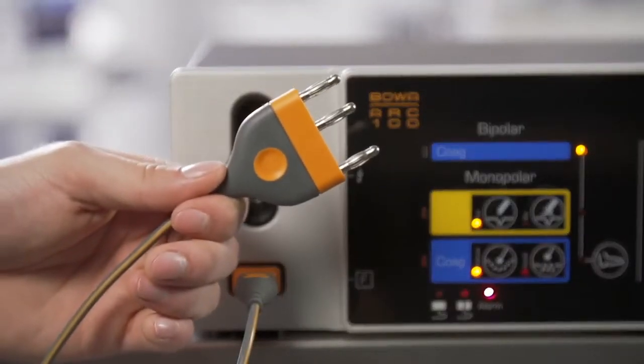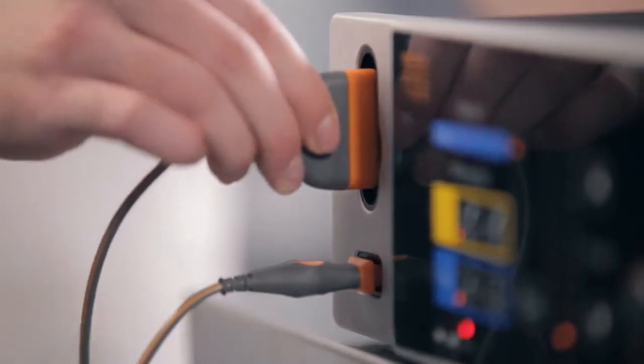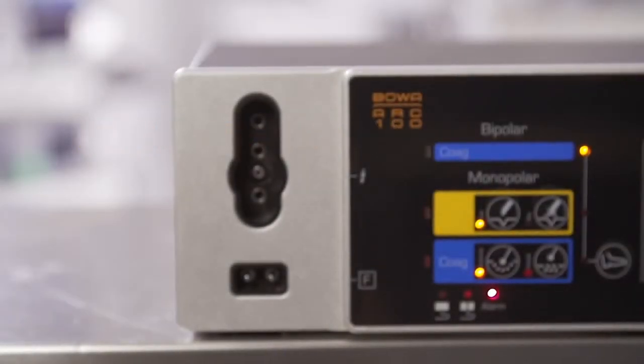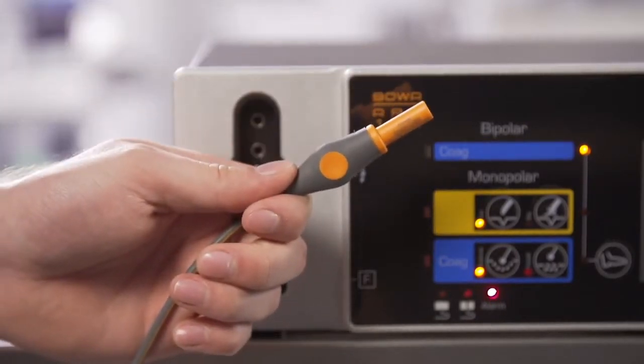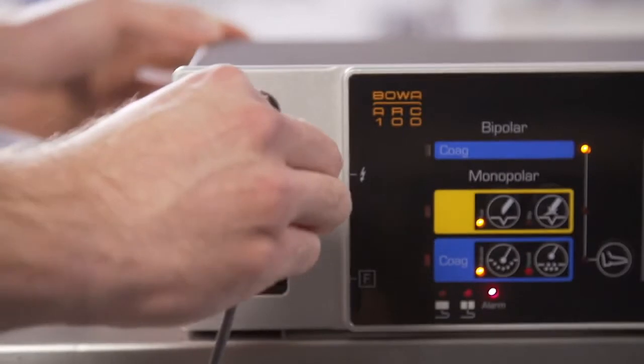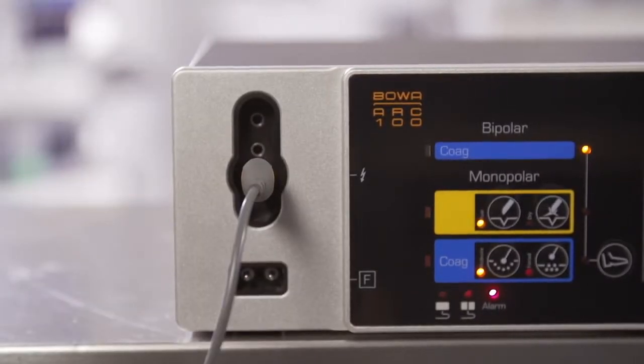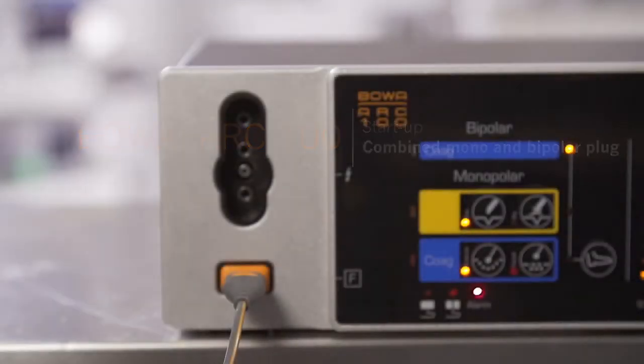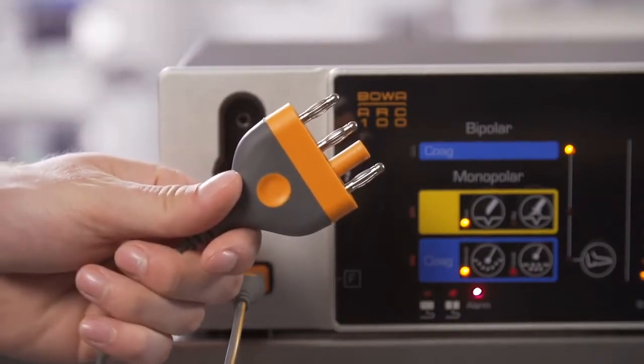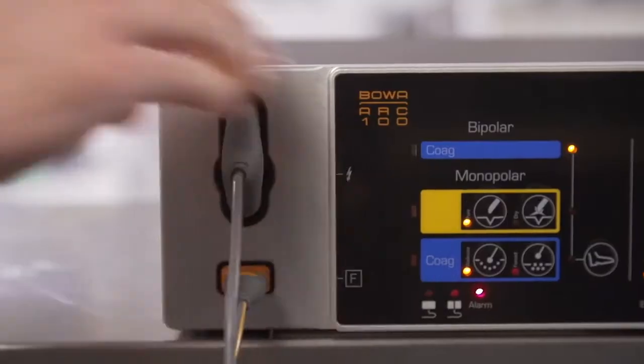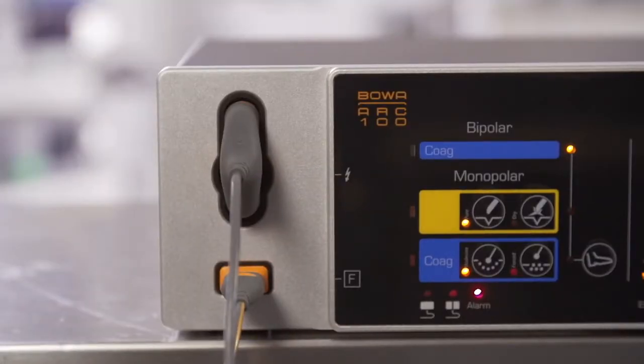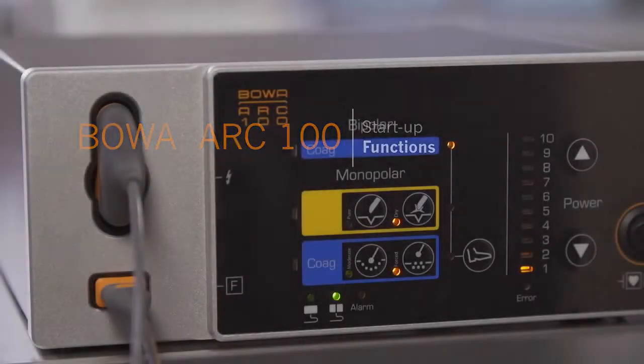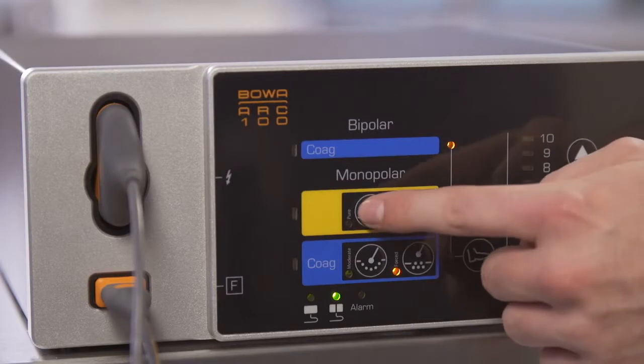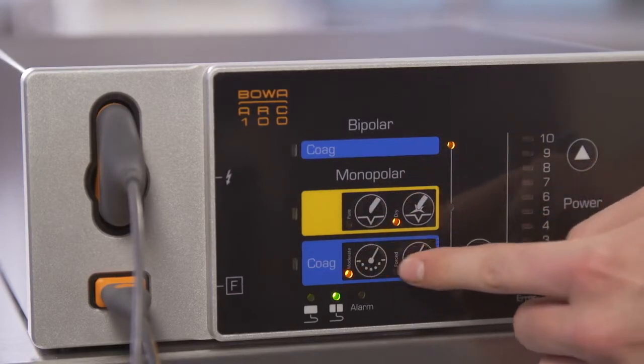Plug the monopolar instrument cable into the ARC 100. Plug the bipolar cable into the central socket of the ARC 100. The neutral electrode cable does not need to be connected for pure bipolar applications. A mono-bipolar multifunctional cable is available for the simultaneous connection of a monopolar handle and a bipolar instrument. Plug the mono-bipolar multifunctional cable into the ARC 100. The ARC 100 has 5 tissue effects. Select your cutting mode and other settings using the mode selection buttons.